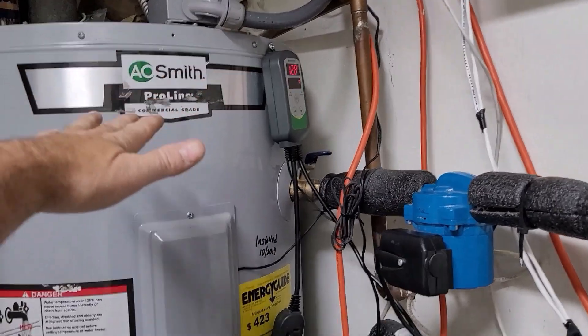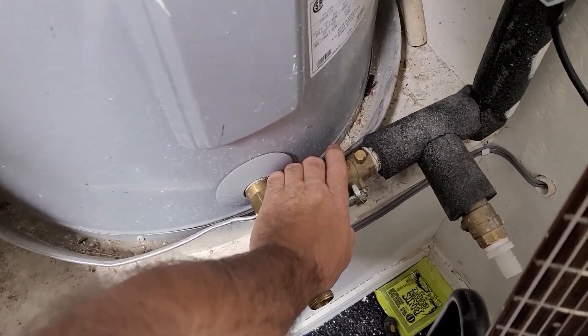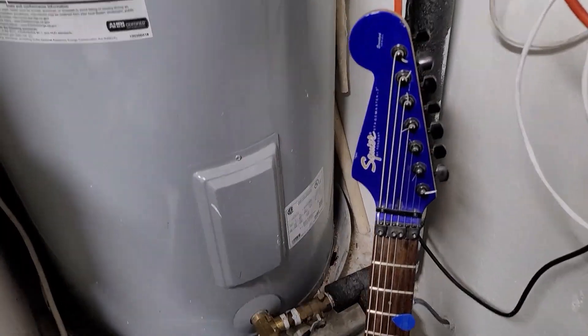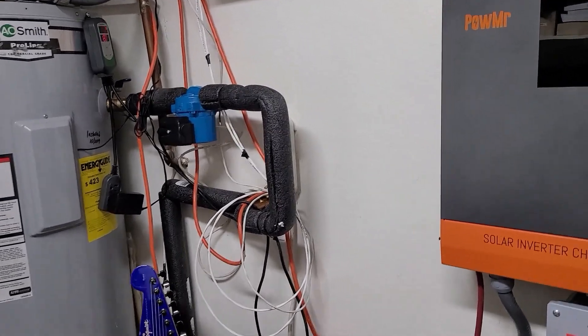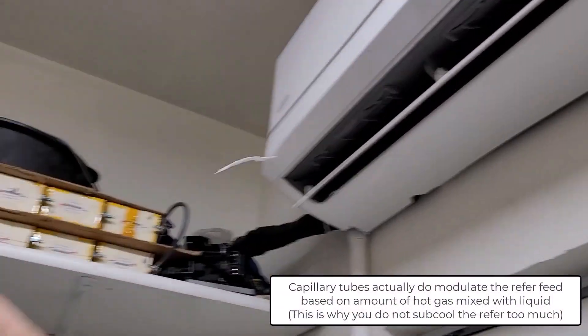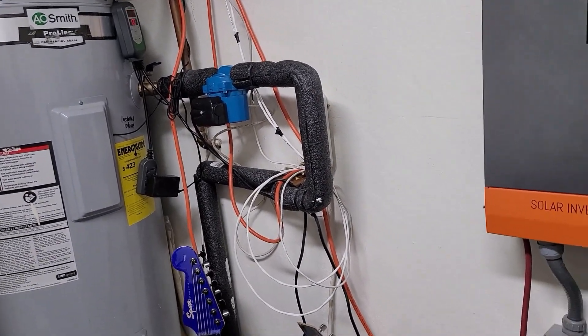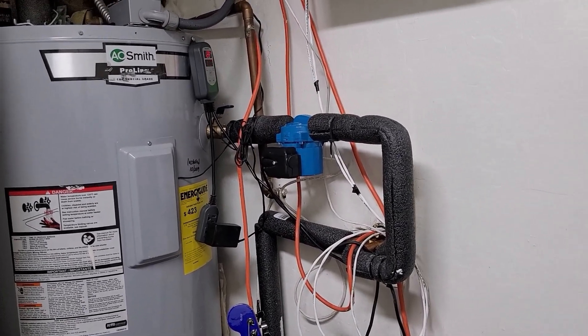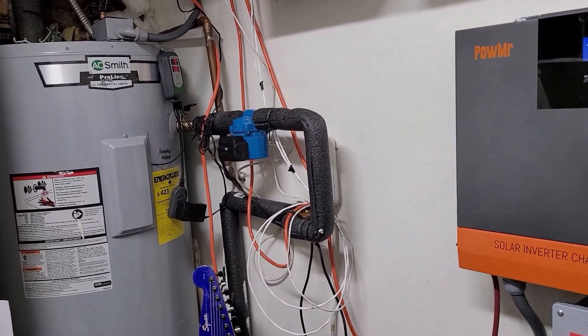What happened was it ran long enough after the water heater was already peaked out that it filled the whole bottom up with hot water — the gradient was pretty much gone and it was like 130 degrees going right to that heat exchanger. My head pressure shot up, and the capillary tubes did what they do: slowed down the metering because you get more hot gas mixed in with the liquid, which slows down your feed. My split temp went to hell — just like what you see with little low-temp units, they diminish in cooling until they hardly work. It wasn't cooling very well at all, so I turned it off. It works great except I need to add another little bit of heat exchanger.